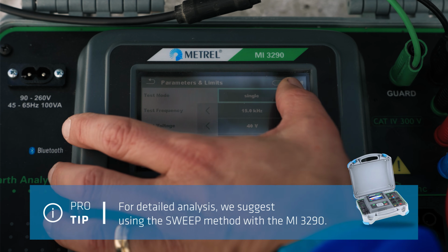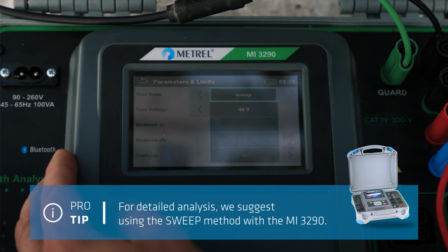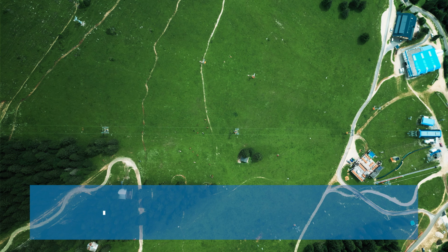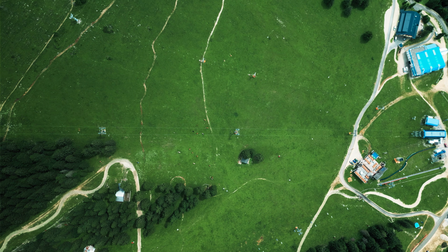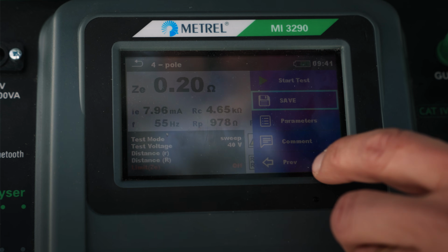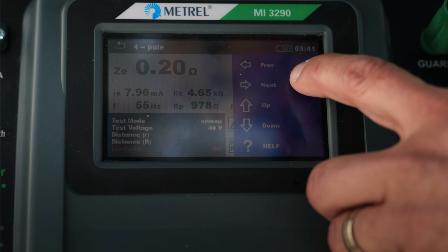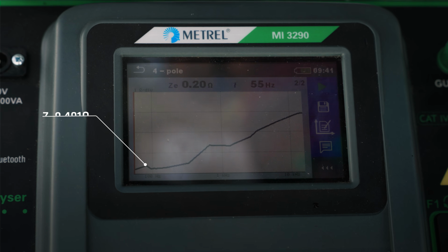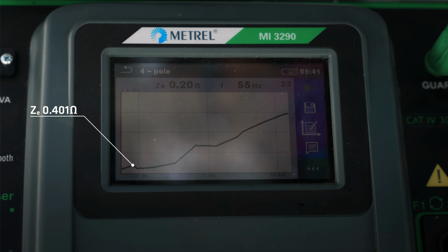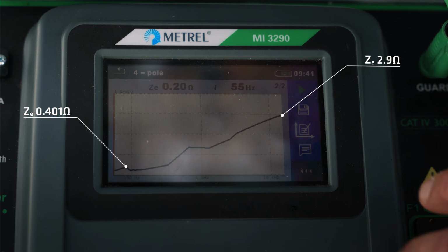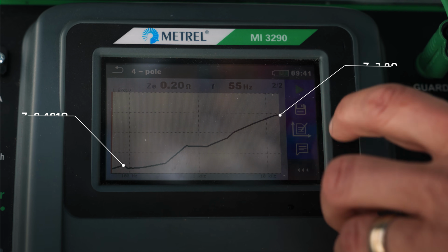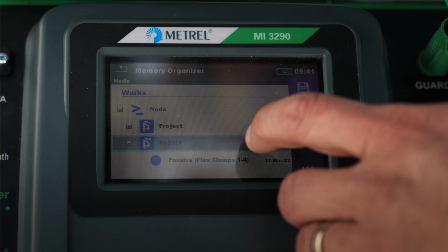For deeper analysis, we use different frequencies during measurements. The sweep function, which was already demonstrated in this video, provides a graphical overview across multiple frequencies and helps us identify both local and distributed grounding characteristics. When towers are connected in parallel by a metal strap, low-frequency testing will show low impedance ZE, for example, 0.401 ohms. Increasing the test frequency reveals more local grounding of the separate tower, so the expected results will be higher.